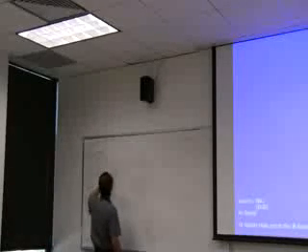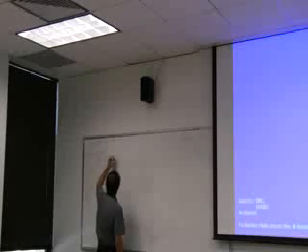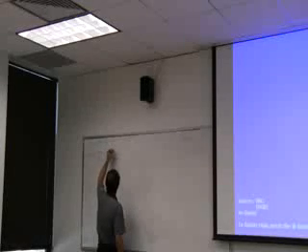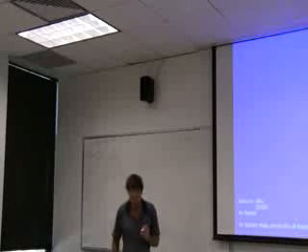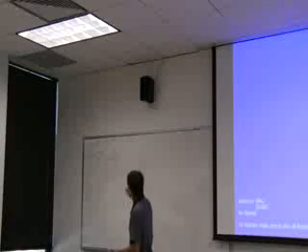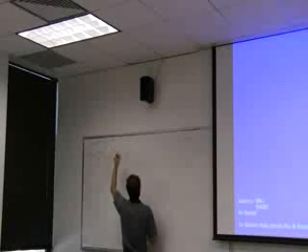And the calibration for that was, I believe, 3,200 pulses per liter. Okay, and I can just invert that and put that on there. That was the calibration? Yes. And now this is going to give me liters per second, so I'm going to multiply that times 60, and that's 60 seconds per minute.